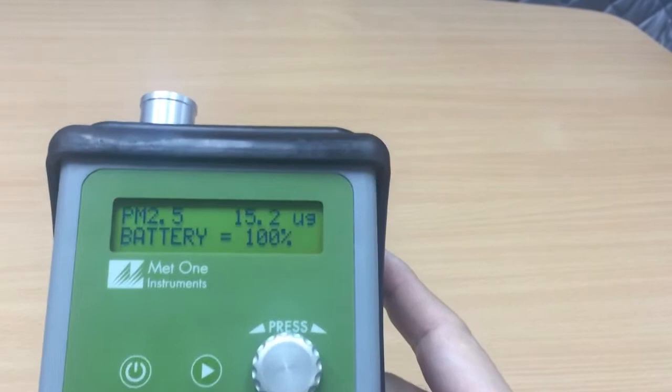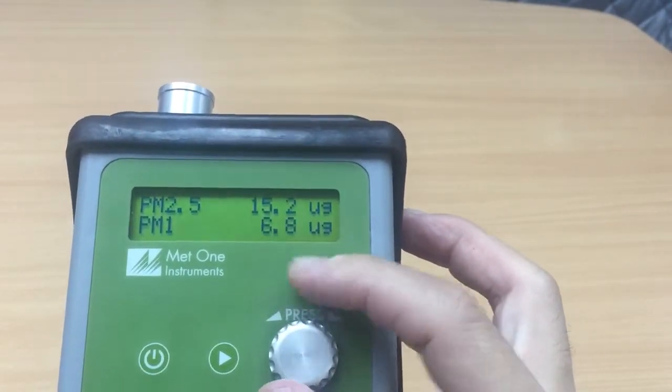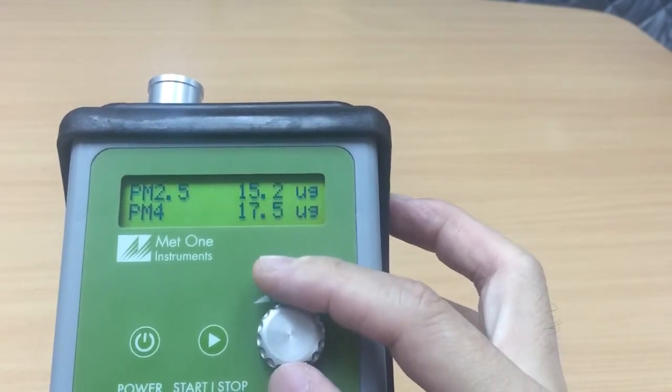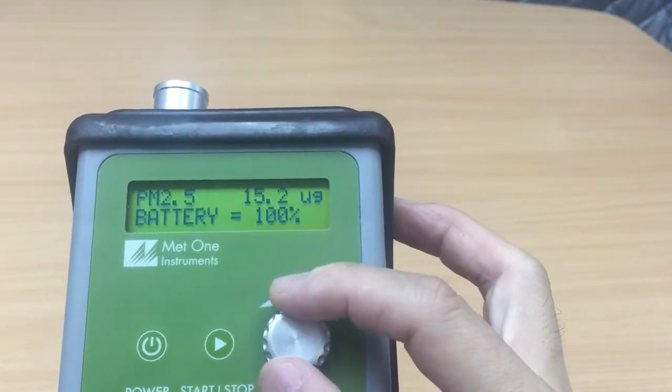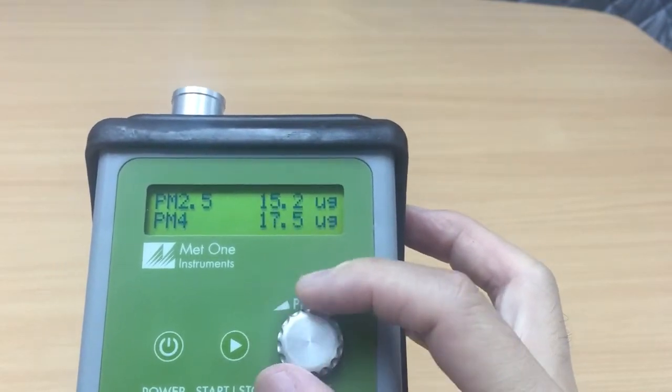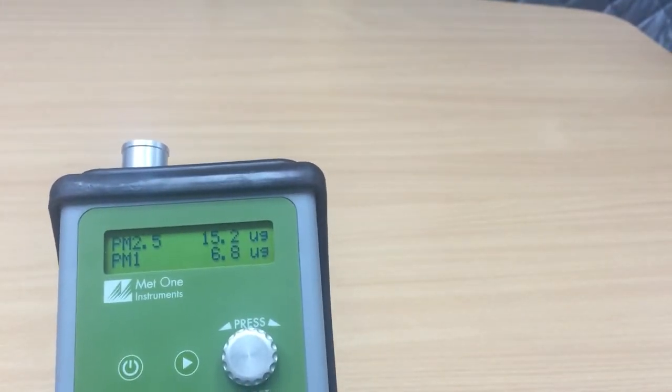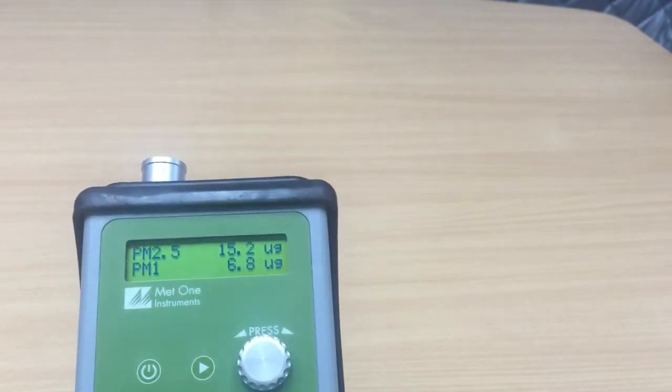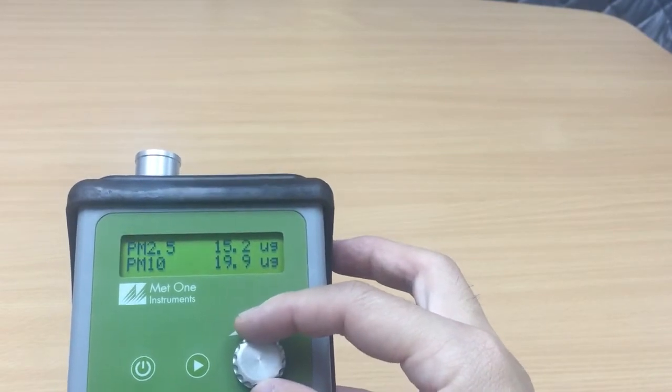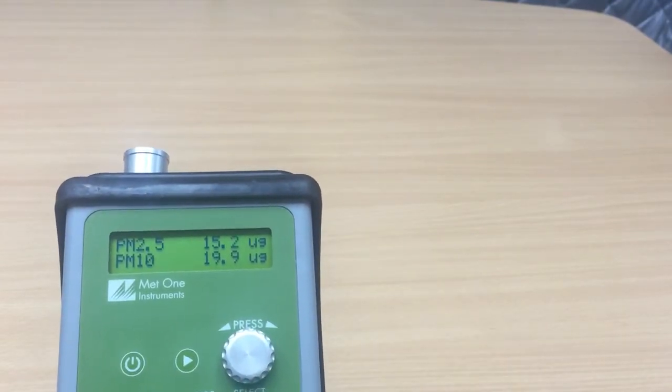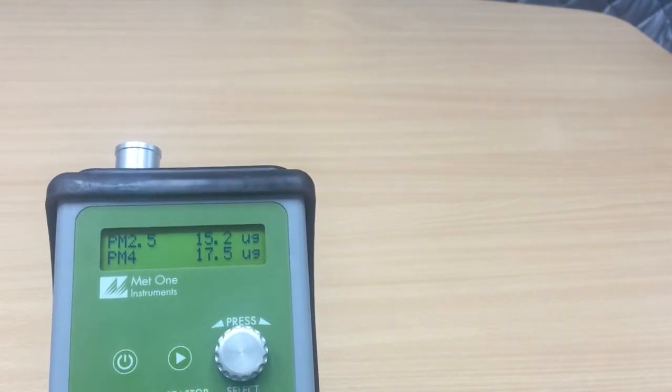Okay we got PM2.5 at 15.2 micrograms and the battery is of course 100%. Let's take a look at others. PM1 is 6.8 micrograms, PM4 is 17.5 micrograms and PM10 is 19.9 micrograms. So this is an indication of how clean or how dusty this particular room is. 15 micrograms is considered still acceptable based on indoor air quality guidelines. Typically the respirable size section is PM4 should be less than 15 micrograms.